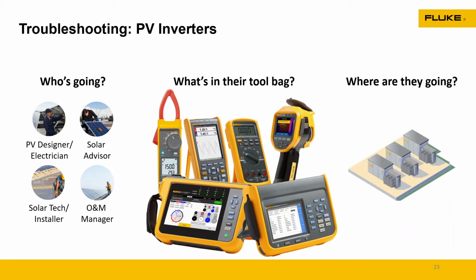We also may need a thermal imager. Maybe we have hot or damaged components in that, and it'd be easily detectable with a thermal imager. But also, we may need some type of power quality unit. With some of the power quality units now, we can do DC load analysis. So we might be able to do an analysis on that DC side of it as well as that AC side and do an efficiency on our inverter and see what's happening.